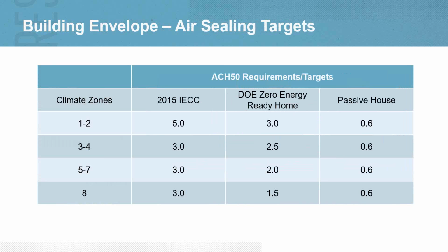As far as air leakage, I mentioned we want to look at those details, put them in the construction docs and work scopes, and then measure. For those familiar, there's a test called a blower door test that a technician runs. It pressurizes the home and measures how leaky it is. We get a metric called an ACH 50 rating out of that test.